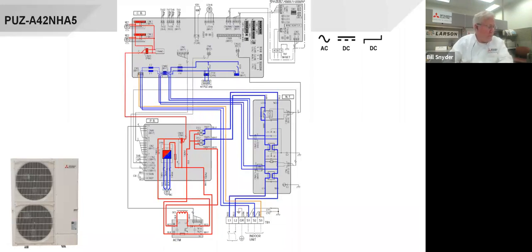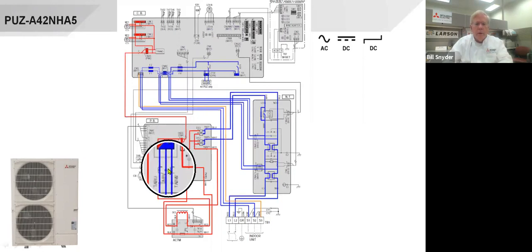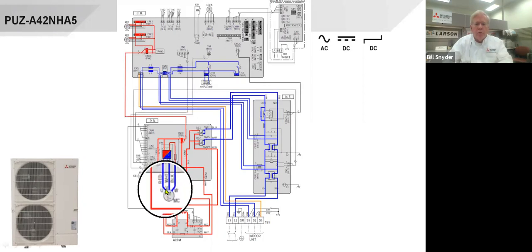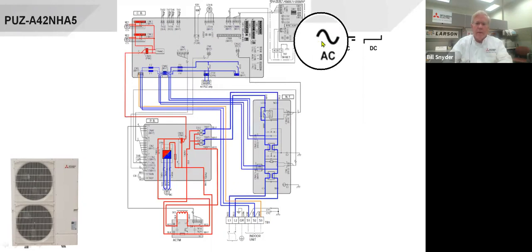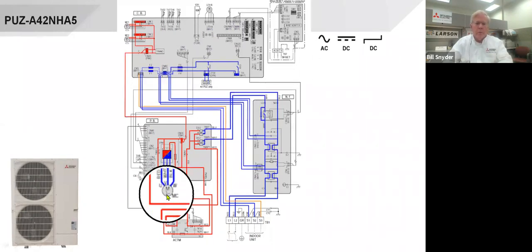I'm trying to think, IPM, Intelligent Power Module is what they call it right here. This is the IPM, and that's the same thing as the insulated gate bipolar transistors we talked about. So that's taking the power. You can see a minus and a plus there, hopefully coming in on the red side, and we come out with AC voltage and we go to U, V, and W to the MC, which stands for motor compressor. You'll also see there's a little 3 and a wavy line behind it, meaning that this is 3-phase. So that's a 3-phase compressor.